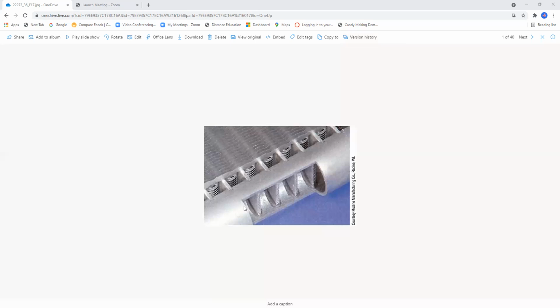Look at how tiny these openings are as far as circulating fluid. This is quite something. From a refrigeration standpoint, if you get a leak in one of these things, they can be repaired, they can be pinched off, but it's a lot of work. Typically, I will not attempt repairs on these microchannel coils. I will turn them into the manufacturer's distributor for warranty replacement.